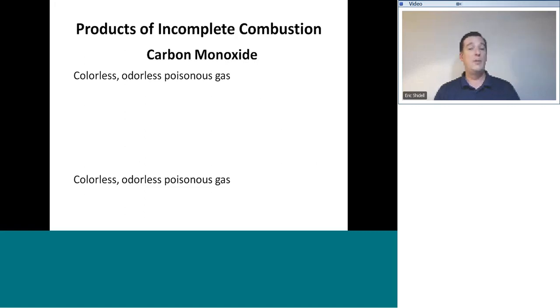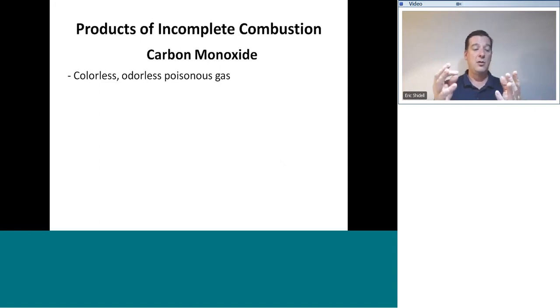be aware that carbon monoxide is a colorless and odorless poisonous gas that kills or injures thousands of people across America every year. And we are really on the front lines of that. Keeping our burners burning cleanly is going to minimize or eliminate the production of carbon monoxide. Remember that carbon dioxide is produced when a carbon and two oxygens link up together. Well, if we don't have enough oxygen present and only one oxygen combines with the carbon, that's carbon monoxide. Carbon dioxide, good in the flame. Carbon monoxide, not good in the flame.